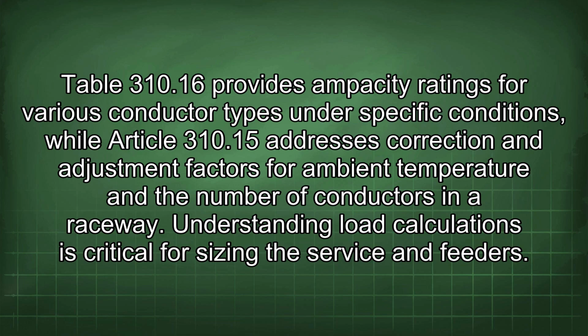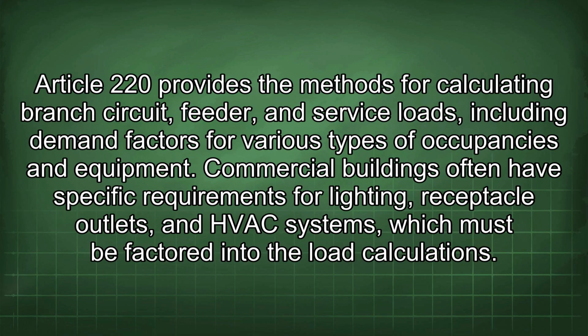Understanding load calculations is critical for sizing the service and feeders. Article 220 provides the methods for calculating branch circuit, feeder, and service loads, including demand factors for various types of occupancies and equipment.